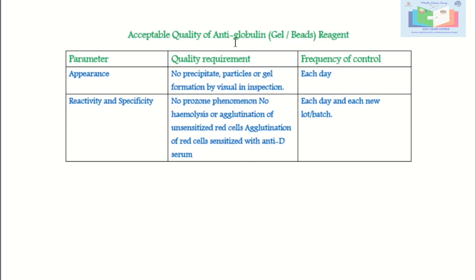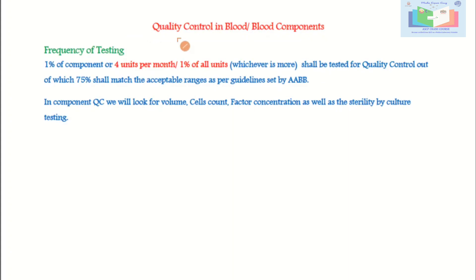Acceptable quality of antiglobulin gel or bead reagents: for appearance, there should be no precipitate, particles, or gel formation by visual inspection each day. For reactivity and specificity, there should be no prozone phenomenon, no hemolysis or agglutination of unsensitized red cells, but there should be agglutination of red cells sensitized with anti-D serum. This is checked each day and requires lot-to-lot verification.